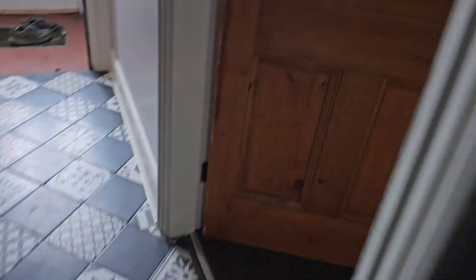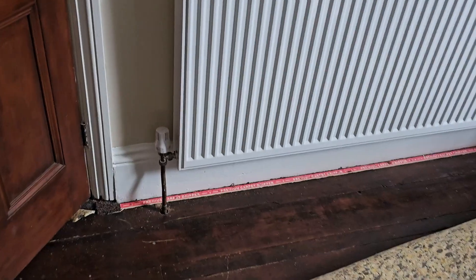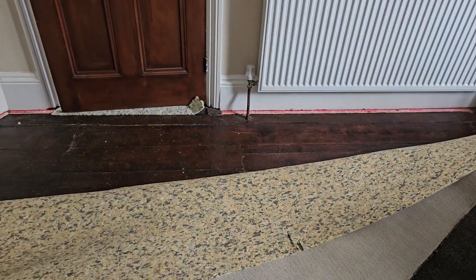So now we've got the pressure test on. Had a little hunt around. Because it's such a large leak, I would have thought it would be in this suspended area around here. Just clear all this away. Let's remove the carpet. The leak — you can hear that hissing. It's either a snake down there or it's the leak we're looking for.